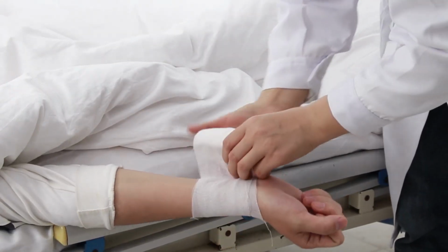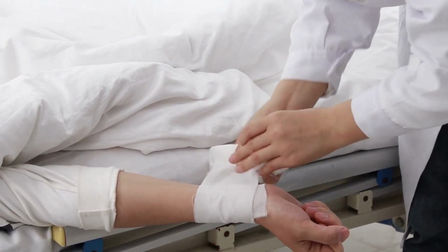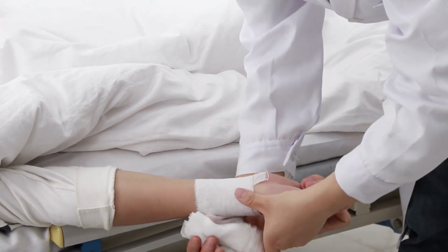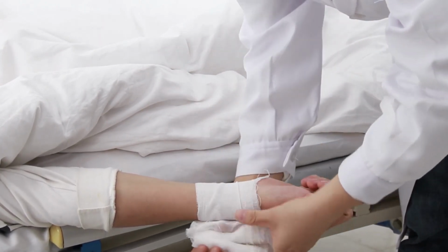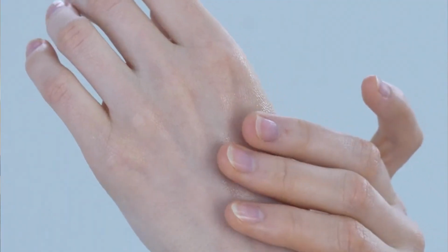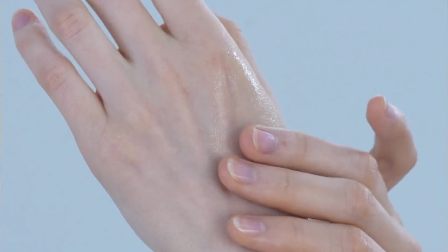So let's look at some examples of products that ISO 14971 covers. First one being bandages. Even though bandages are very simple devices, they still need to be manufactured and used in a safe way. ISO 14971 can help manufacturers identify and mitigate any risk associated with the bandage, such as the risk of contamination or skin irritation, and so on, right?